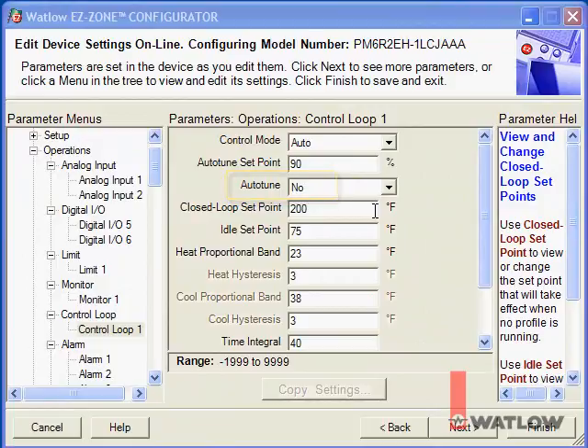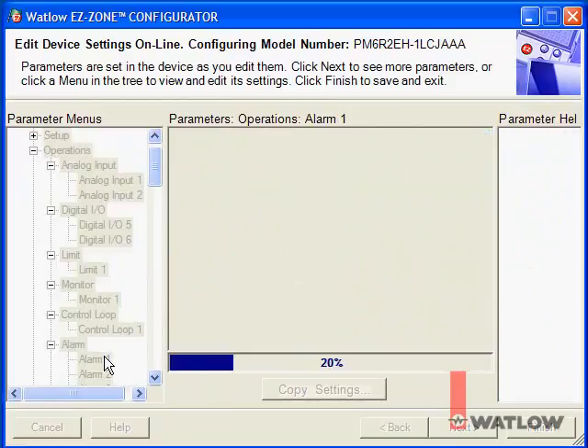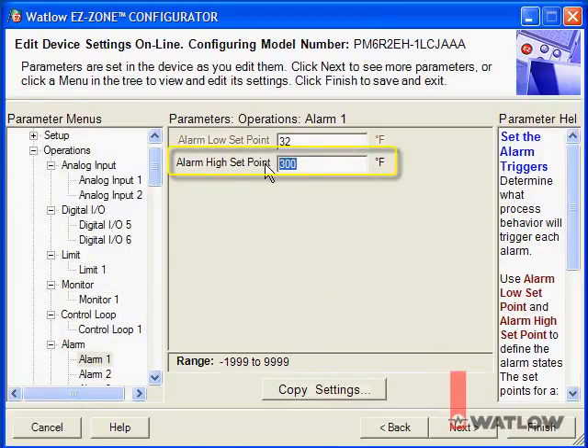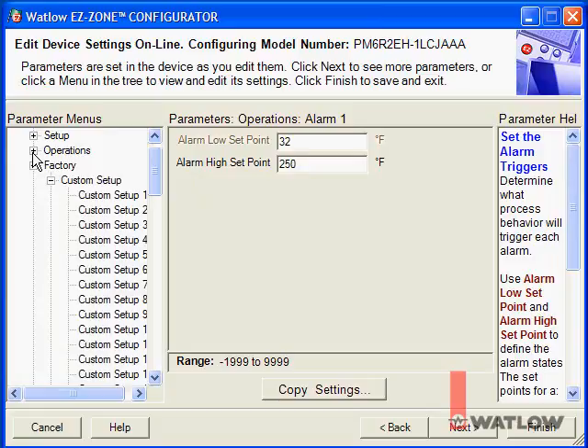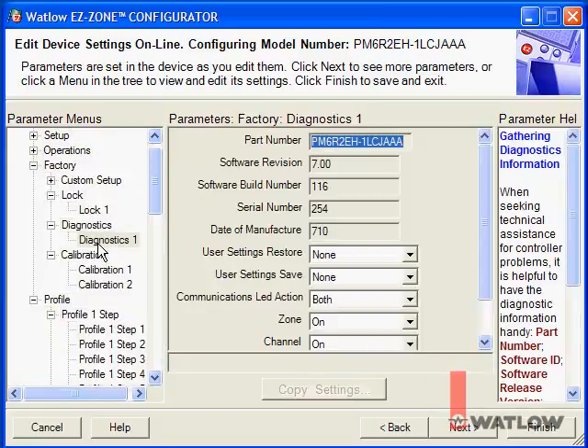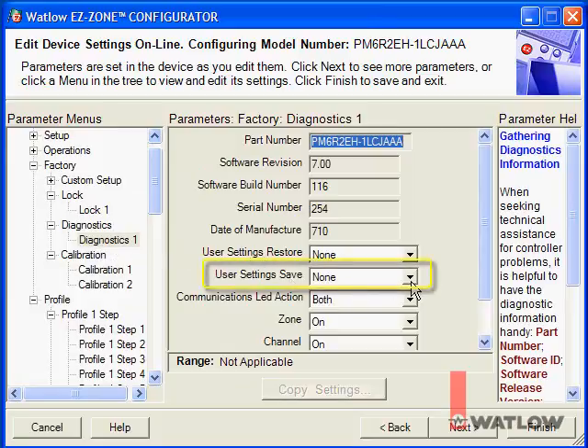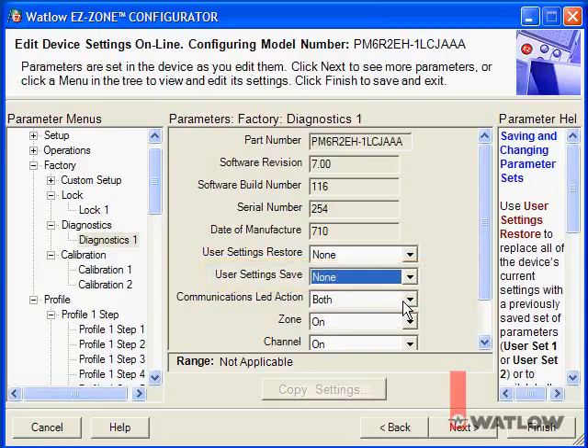Now that tuning is completed, I'll set the high process alarm setpoint to 250. There are many other settings in this controller, but we've set everything necessary for this application. Other parameters can be used for ramp and soak profiling, customizing and locking out the controller menus, calibrating the controller, and many other features. The last thing to do is save the settings. You don't have to do this — the controller will remember the settings — but just in case someone mistakenly changes a setting later, you may want an easy way to get back to a known good state. On the Diagnostics 1 menu, let's save the settings as User Set 1. You may also want to save the settings on the computer so that next time you set up a controller for this application, you can just download the settings instead of setting each one again — it saves time and is more accurate.